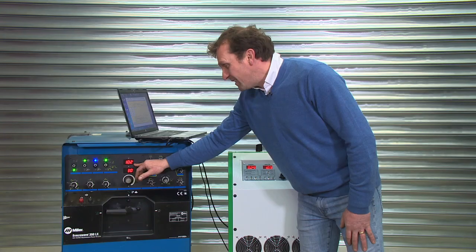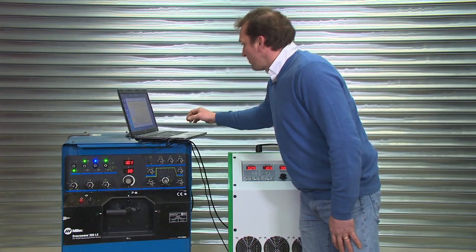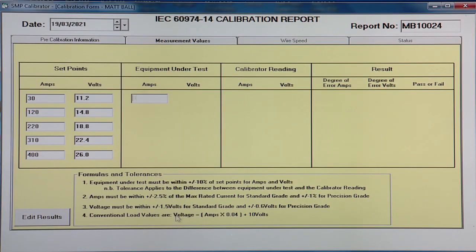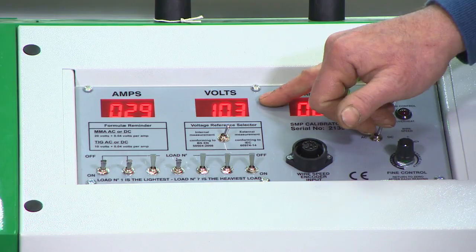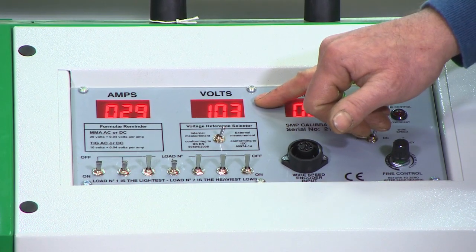So now we have the welder reading 10.2 and 30 amps. We put that in the program. And the calibrator's reading 29 amps and 10.3.